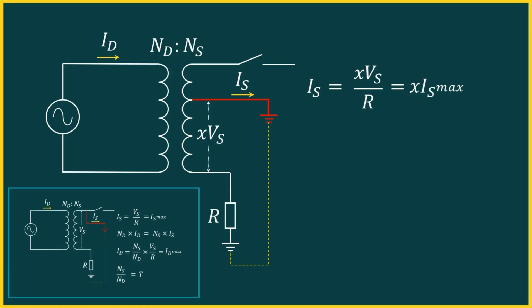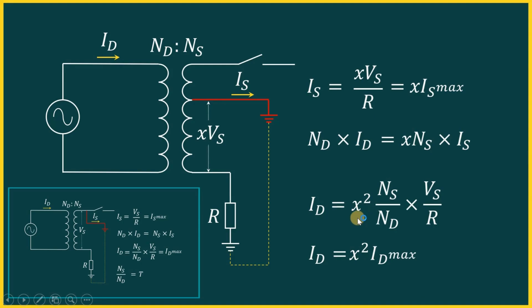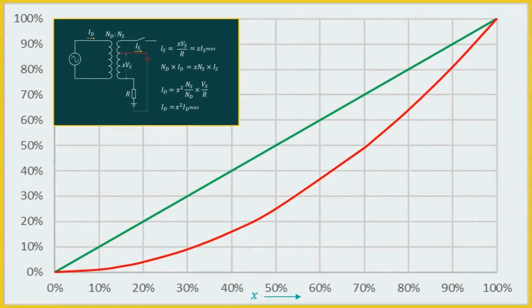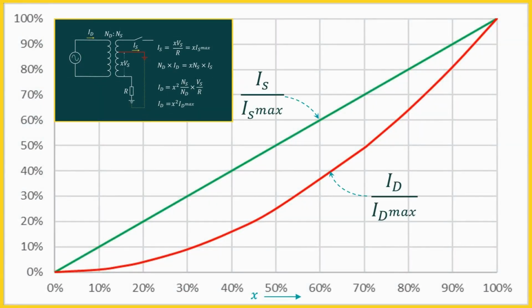Again, to find the delta side current, we can apply ampere turn balance. Here is an important point to note. The effective turns on the star side will be X times Ns, not Ns. So the delta side current will be X square times turns ratio multiplied by Vs upon R. From these equations, we can observe that when an earth fault occurs on the star winding, the current on the star side varies proportional to the distance from the neutral. However, the current on the delta side does not vary linearly. It increases with the square of the distance from the neutral.